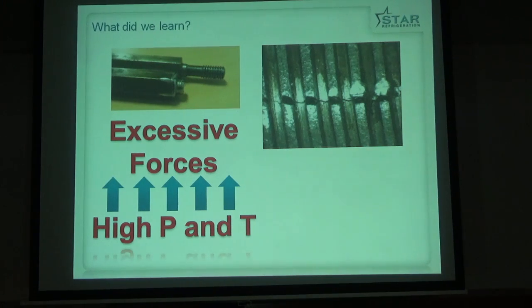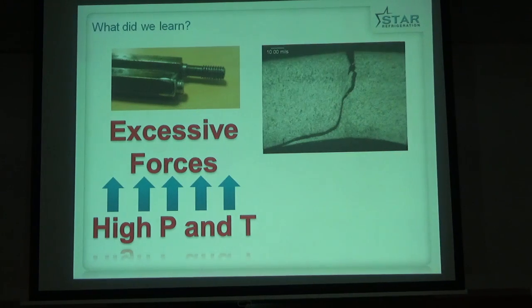If we'd been running at normal operating conditions, we would probably never have known this. But because we're running at 90 degrees C condensing, which is about 65 bar, the defects weakened the tube to the extent that it leaked. And there's a cross-section of the tube. You can see that the crack has propagated all the way through from the initial flaw at the surface.